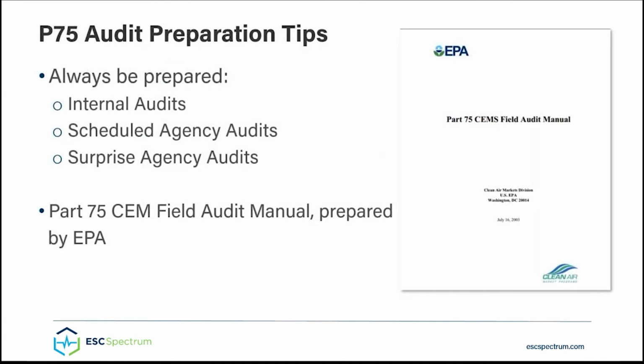Now that we've covered the DAS, we'll close with a few Part 75 audit preparation tips. It's important to always be prepared because audits are not always announced ahead of time. The first thing you should do is download EPA's Part 75 CEMS Field Audit Manual. This manual is used as a guide by EPA's field auditors, so it'll give you valuable insight into what they'll be looking for if they should audit your facility.